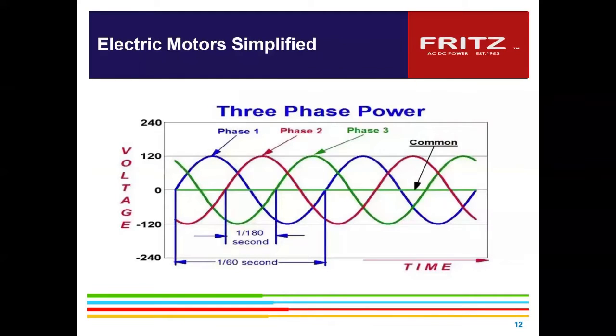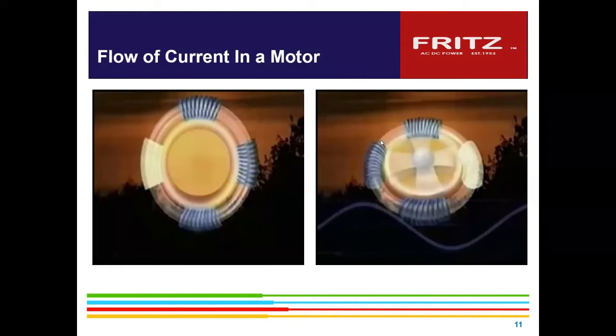So in a power circuit, you have 3-phase power, which is most industrial applications. You can see that there are 3 sets of sine waves: phase 1, phase 2, and phase 3. Those are feeding into the motor, so you actually have 3 sets of coils, one for each phase. This would be more like a single phase machine, but a 3-phase machine would have more coils crammed in here. And then they rotate that field.